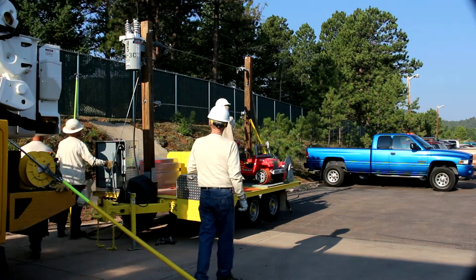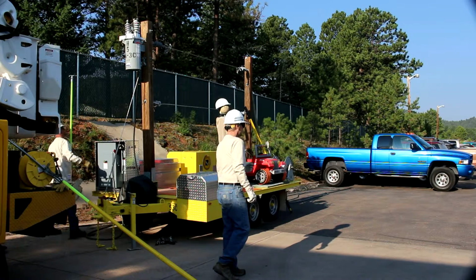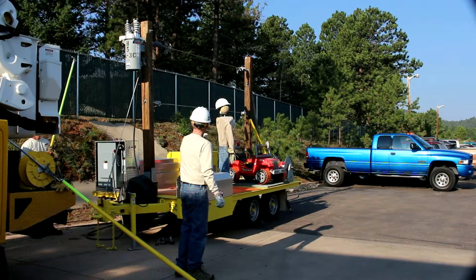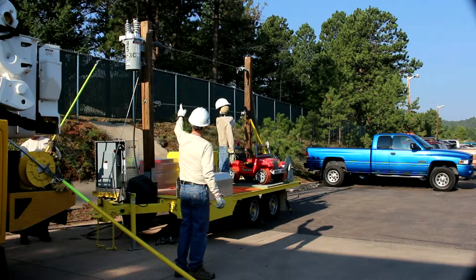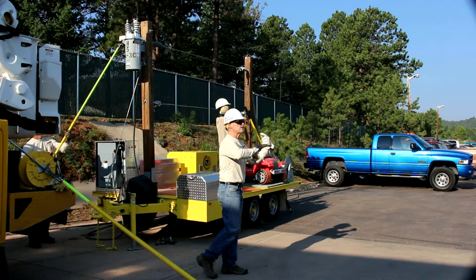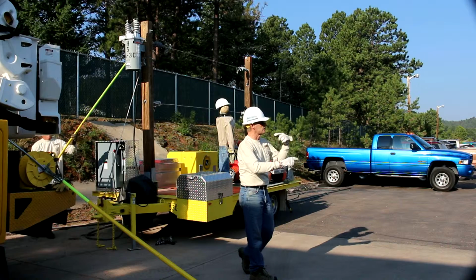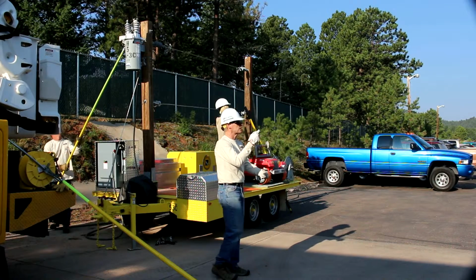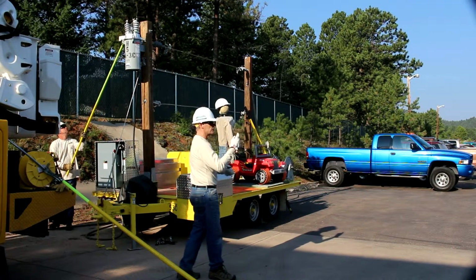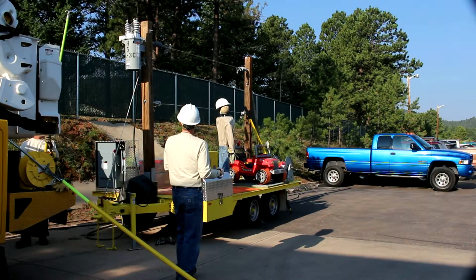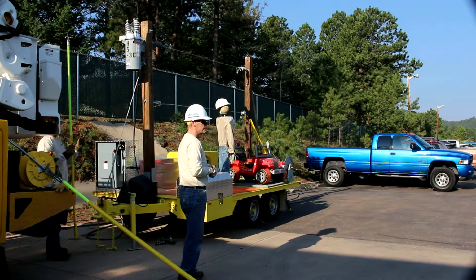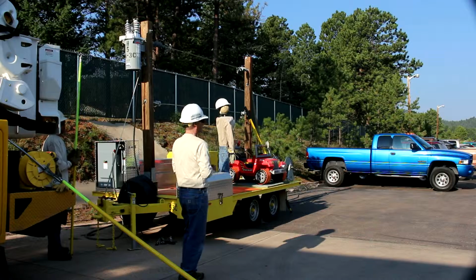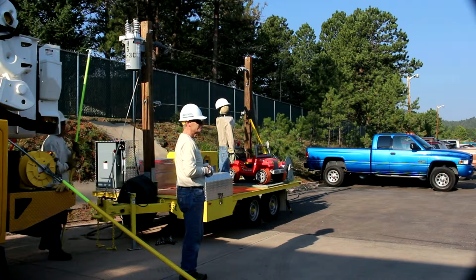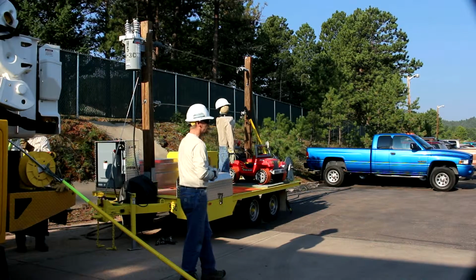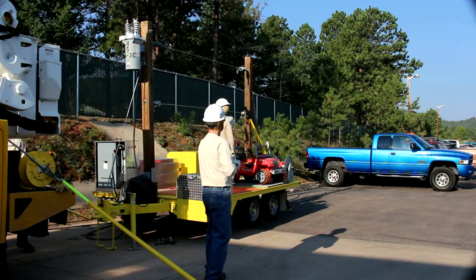First, we're energizing the transformer. We've energized the transformer - it's back feed, so it's coming up our cable. A transformer, you can feed it either way: feed it in 7,000, it comes out 120; feed it in 120, it's going to come out 7,000. It's just a reverse. Did you hear it? You heard me click that, but did you hear the electricity go in the line? No - it's there, can't hear it, can't see it. So just assume it's always hot.